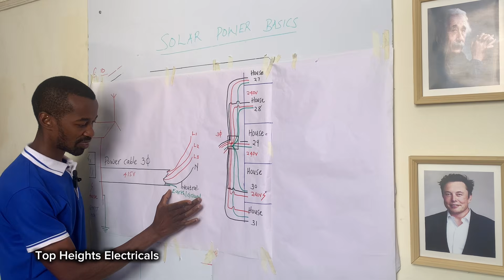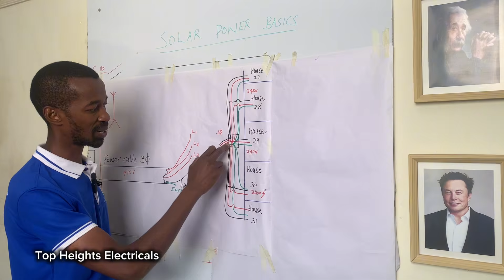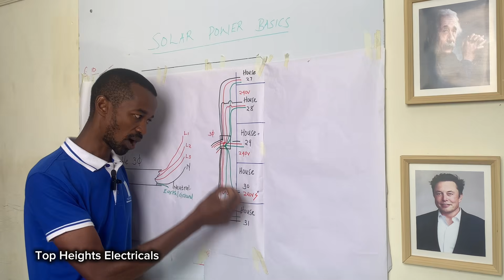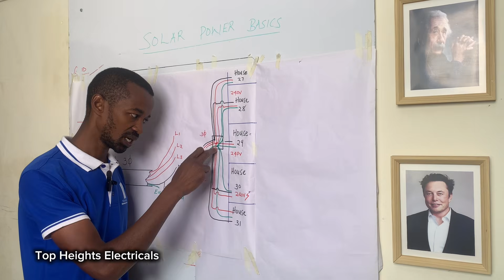Now, the other reason is this: if this earth connection, especially the termination which is insulated by insulation tape, is compromised, number one, by oxidation, whereby we have aluminium and copper in contact.